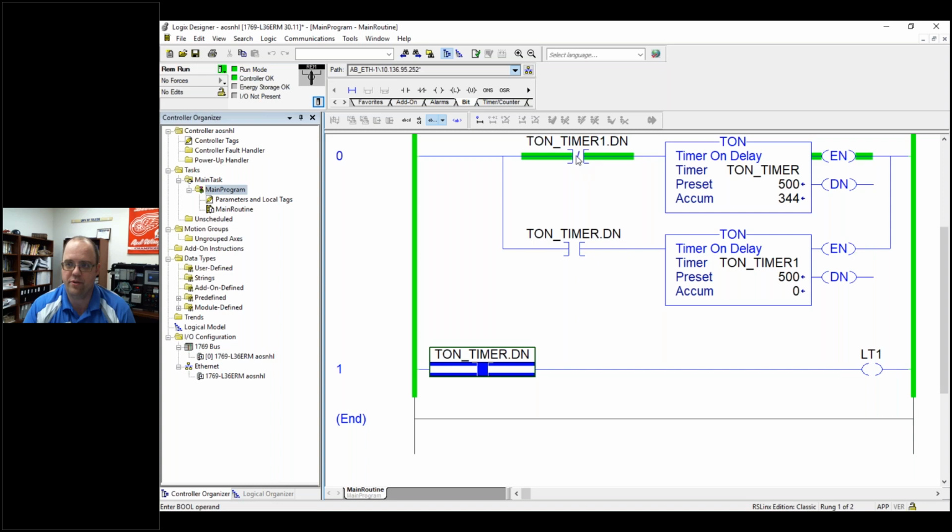Because you don't notice this dropping off, since it only drops off for a millisecond or one scan cycle. But this is basically staying on the whole time. And notice, this is self-resetting. This is a self-resetting setup. If you use the XIO with the done bit of any timer, that's a way of resetting stuff. And I could do this till I'm blue in the face. It's called cascading timers.